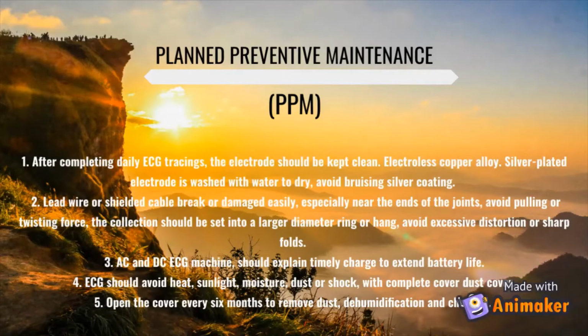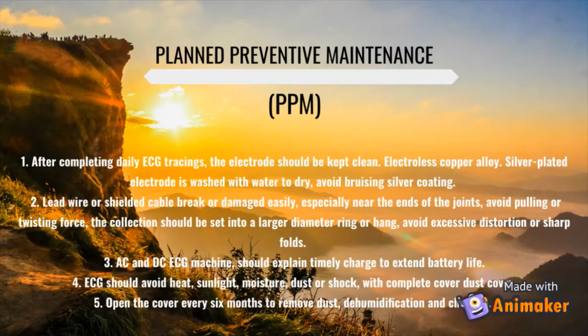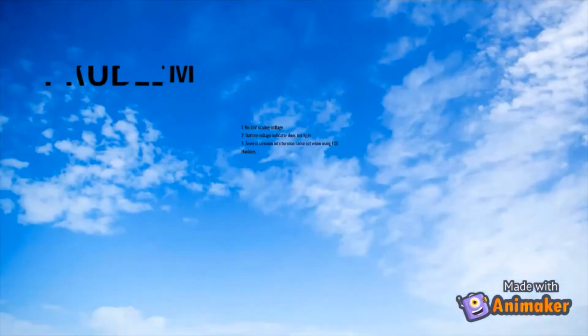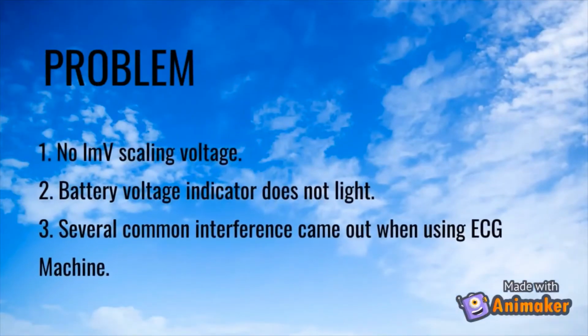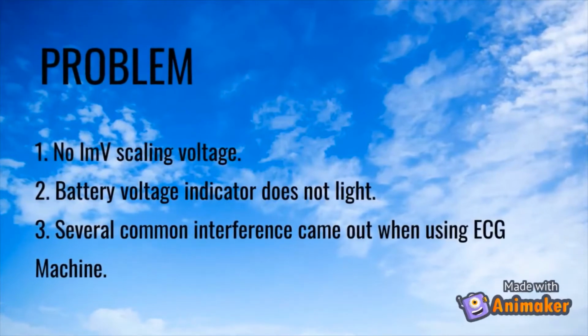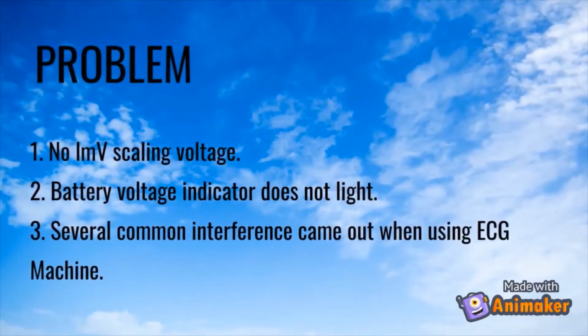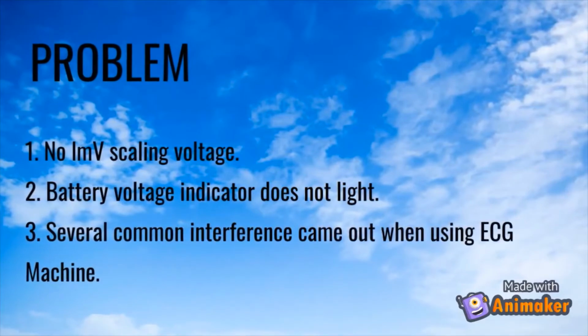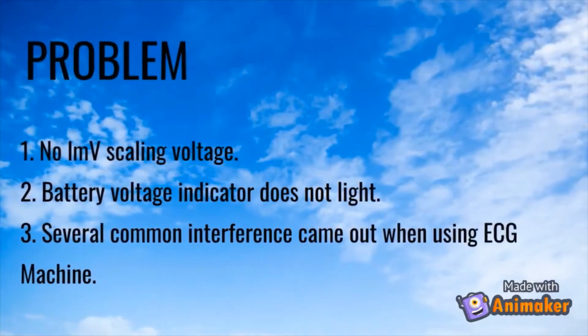AC and DC ECG machines should be charged in a timely manner to extend battery life. The ECG should avoid heat, sunlight, moisture, dust or shock, and be kept with a complete dust cover. Open the cover every 6 months to remove dust, dehumidify and check. Problems faced: no 1mV scaling voltage, battery voltage indicator does not light. Several common interferences come out when using the ECG machine.